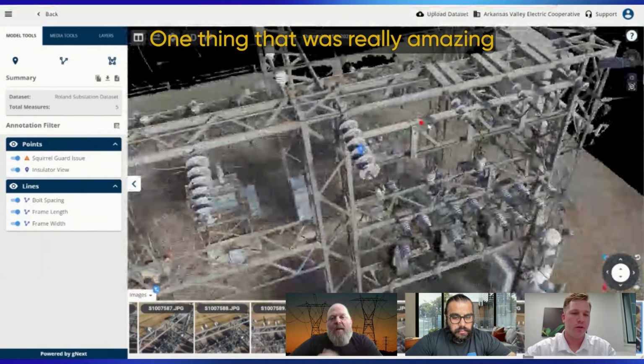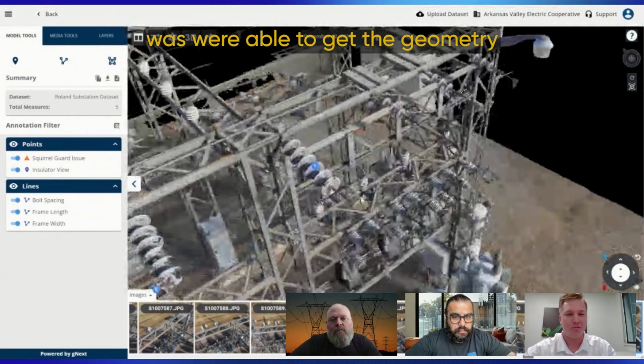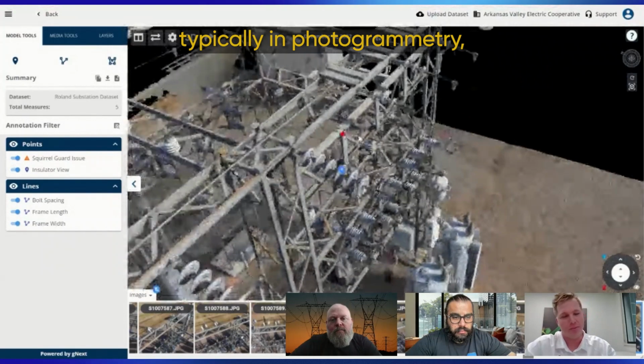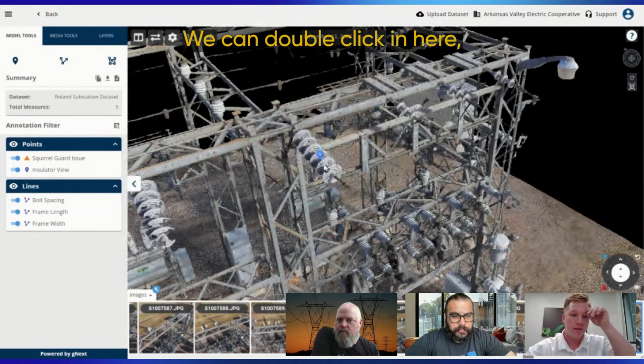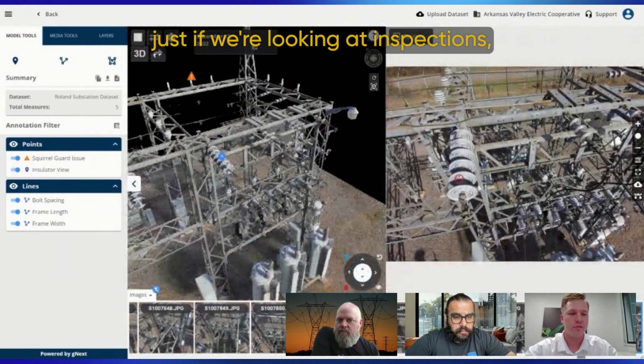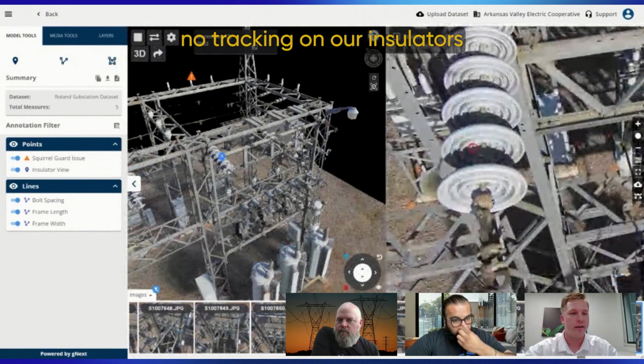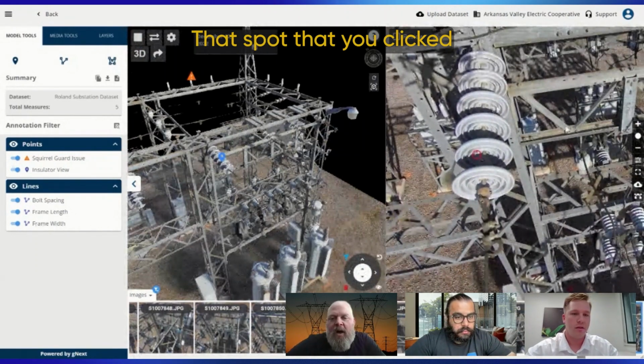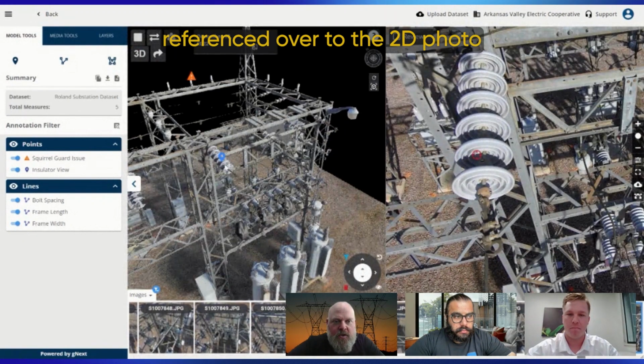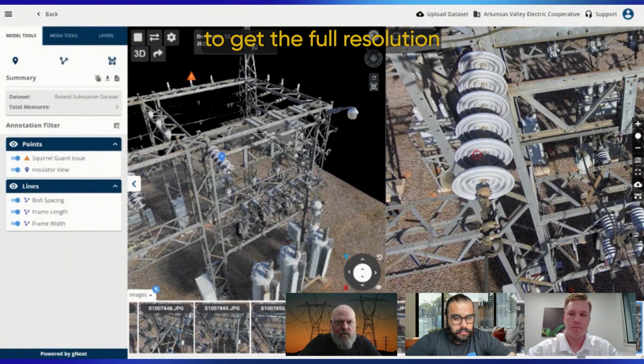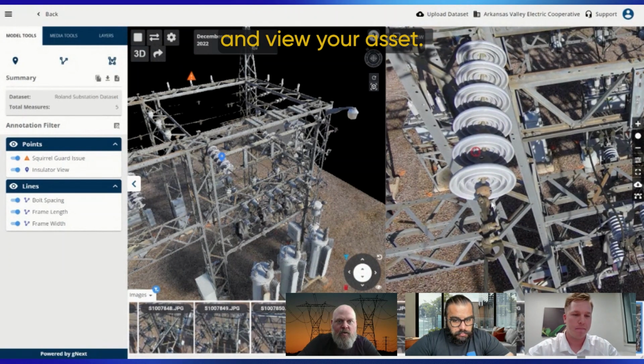One thing that was really amazing was getting the actual geometry out of these insulators—typically in photogrammetry you just get a cylinder. We can double click in here to check health and tracking on our insulators. The spot you click on the 3D model is referenced over to the 2D photo used to create that model, so you get the full resolution image and can really get in there and view your asset.